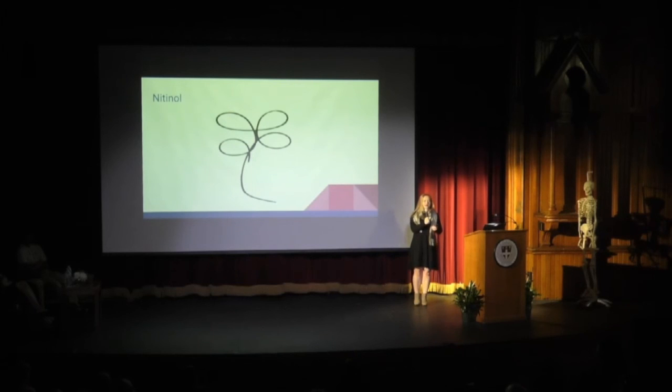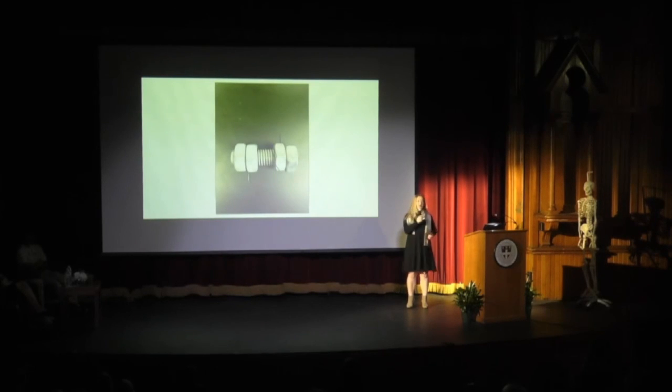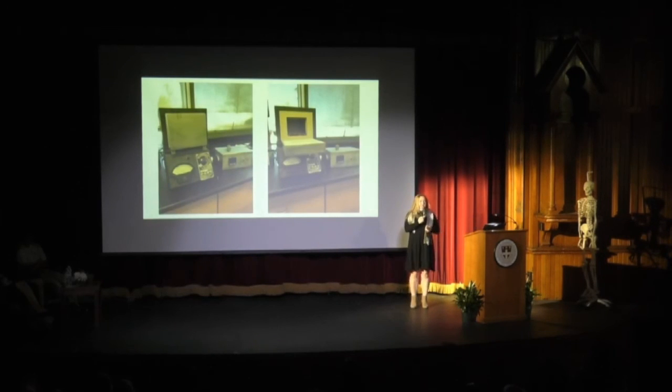Nitinol is an extremely unique alloy, as it has something called memory. So no matter how much you try to bend or maneuver the wire, it will always return back to its original shape. Now the tricky part is actually shaping the wire into a new original position, which in my case would obviously be a spring. One of our biomedical device engineers, Jim Picorni, helped me to do this. So first we had to wrap the wire around a bolt and then secure each end of it. Then the nitinol wrapped bolt needs to be heated to around 1,000 degrees Fahrenheit in this small box furnace.